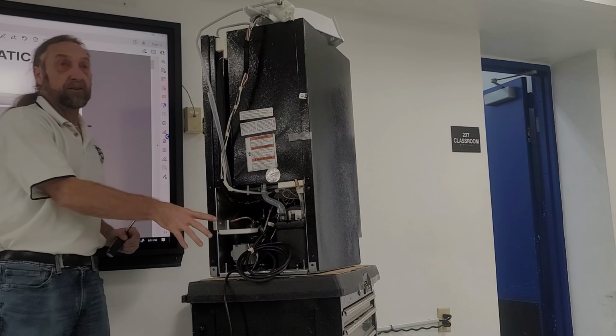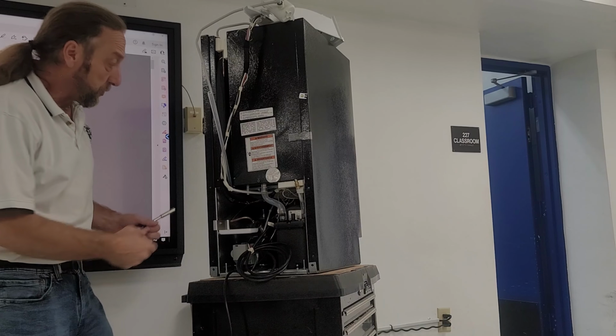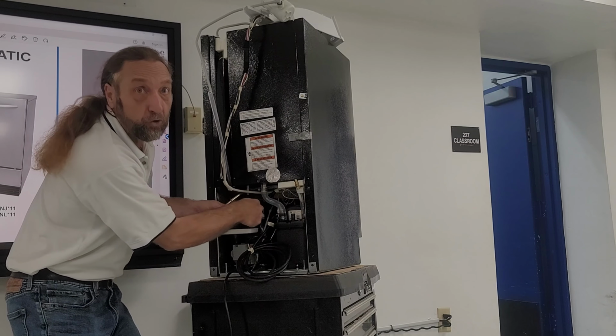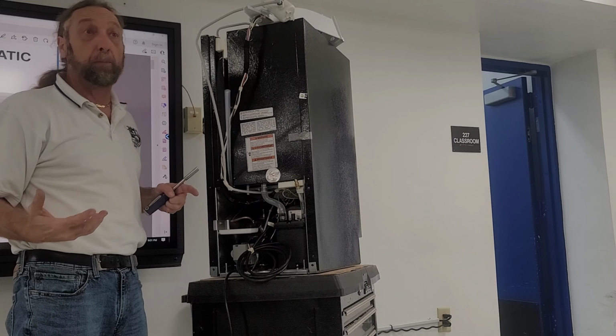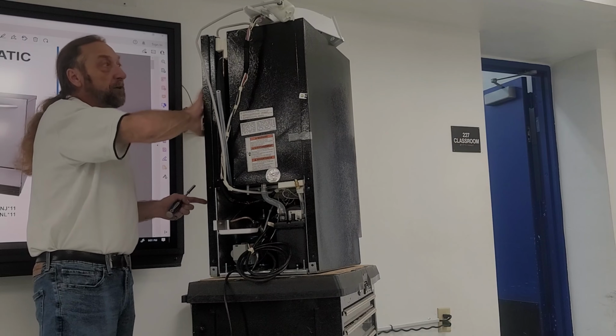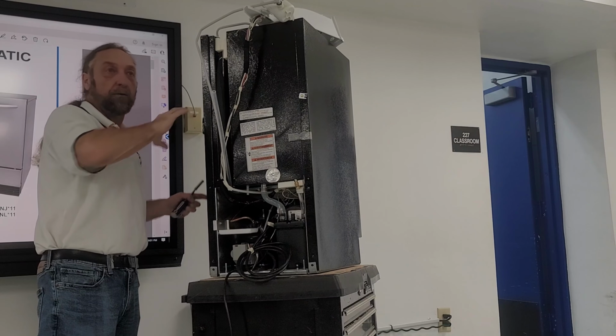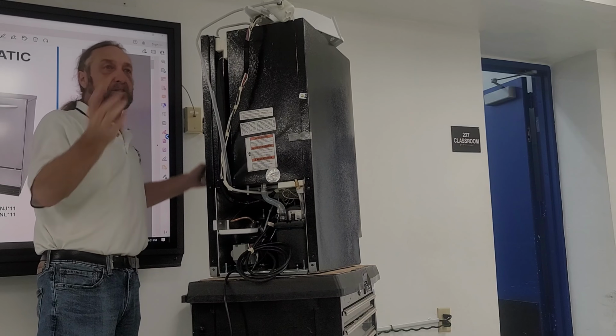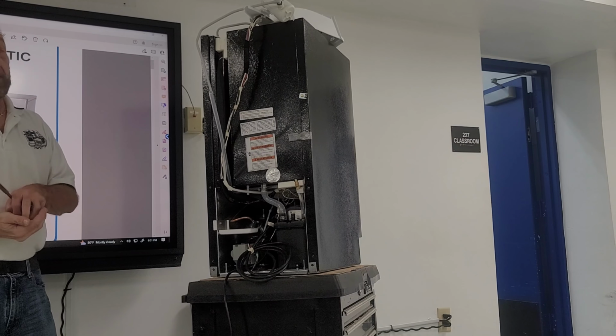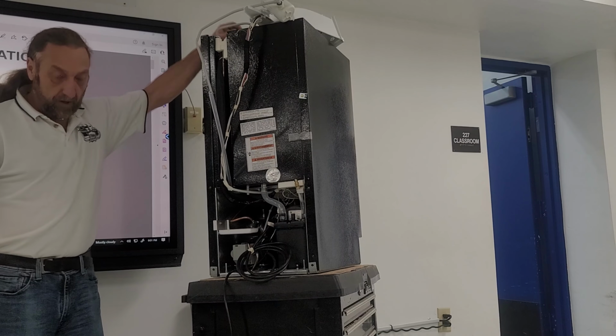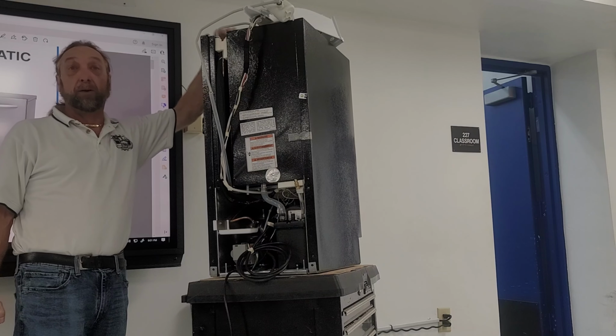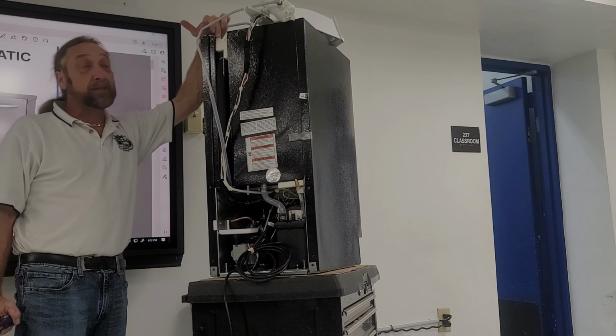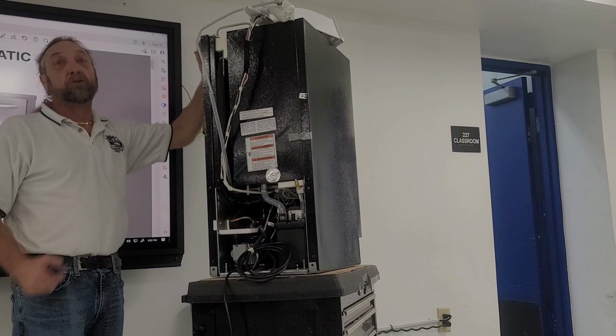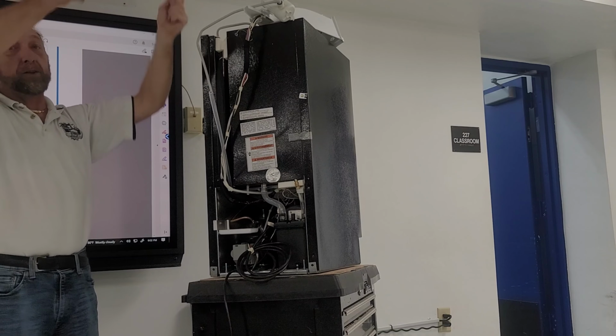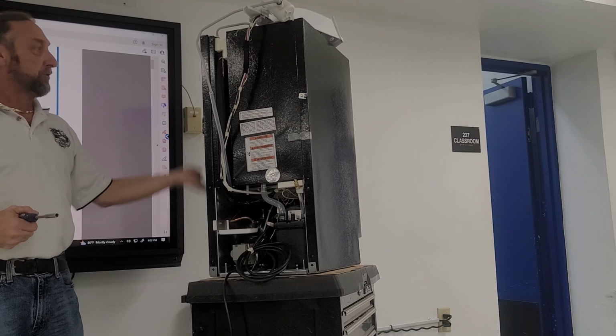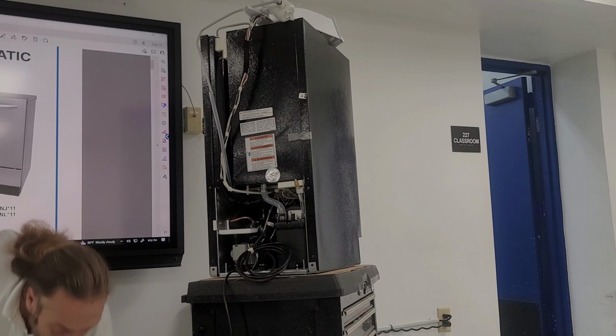So if you're doing a sealed system job, unlike a refrigerator where you're right in there trying to get a torch in, unable to see and afraid of burning stuff up, on this unit we can take the whole cover off, service the sealed system, and put the cover back on. But to take this off, you have to remove the evaporator from inside—not disconnecting the lines, just unscrewing it and lifting it up and over the back of the unit so the whole cover comes off. Let's see if we can do that.